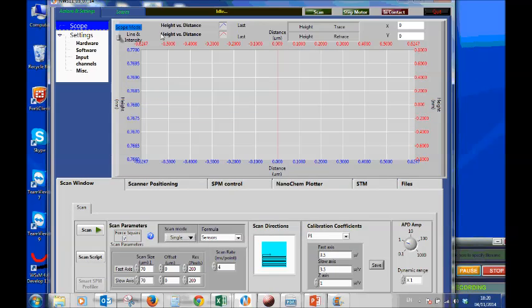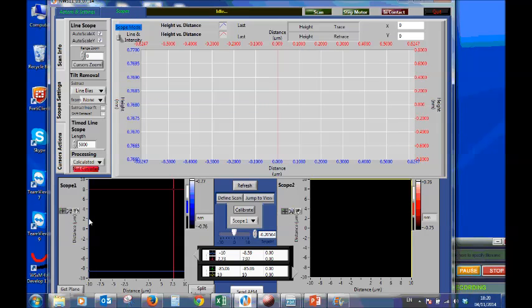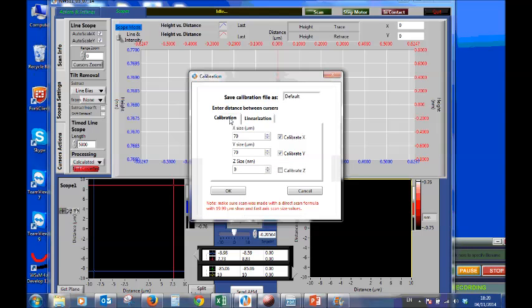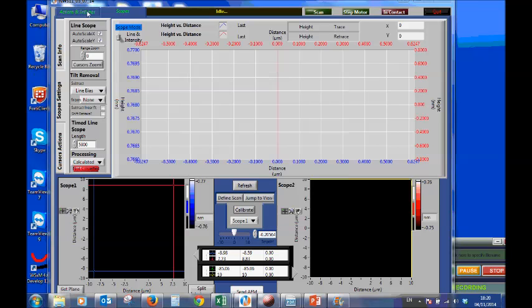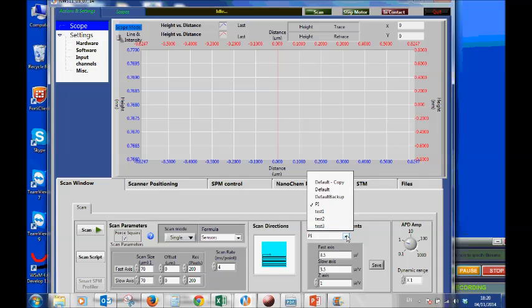and when we're done scanning, we choose with the cursor a certain area, which we know the dimensions. We go to calibrate, and then the important thing here is to choose calibration, not linearization calibration. We do calibrate X, calibrate Y. We give it a name, for example, test 2 or test 3. Wait. We don't press enter, we press OK. And then first we can choose here the correct Z calibration coefficient, because we're not dealing at all with the Z. So the Z has to do with the scanner and not the sensor. What we're interested in is the formula here. So we're going to choose test 3.